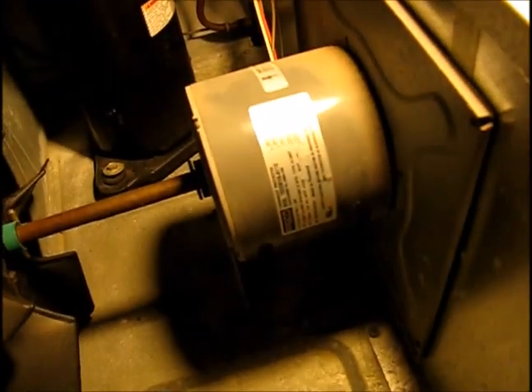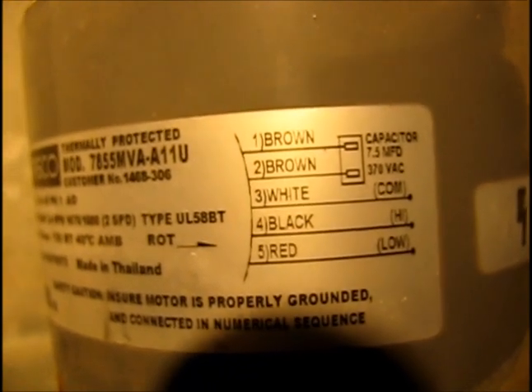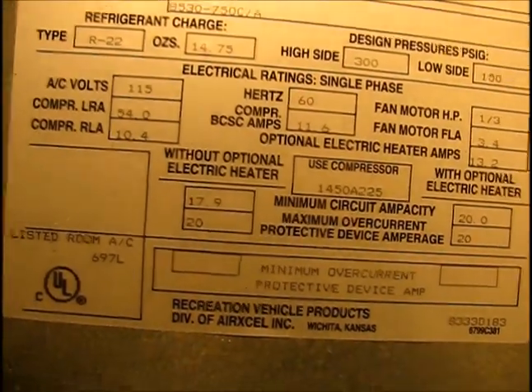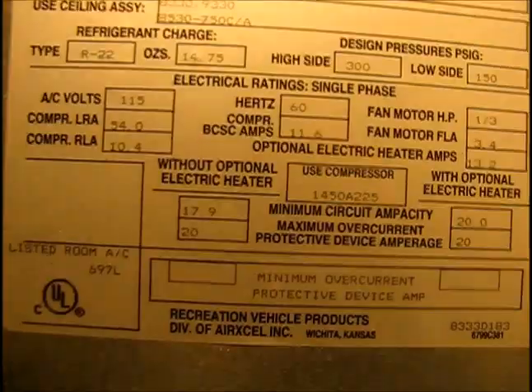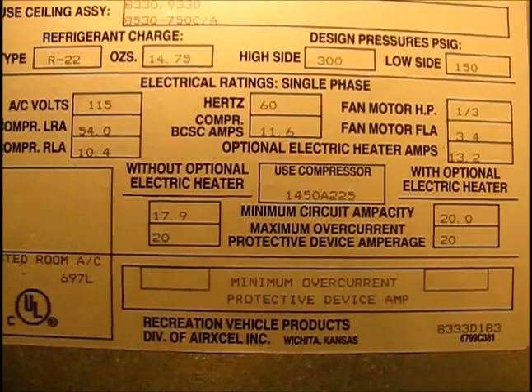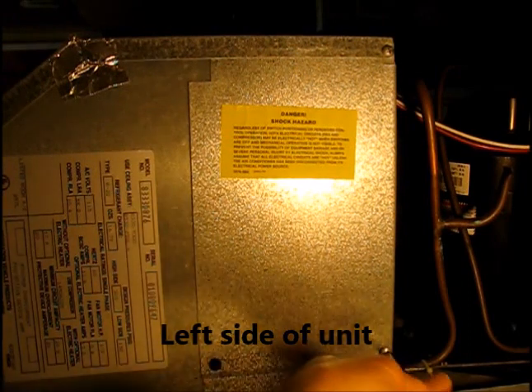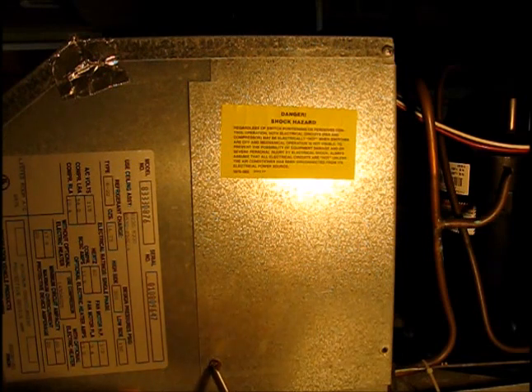Both sides off — now we can lift it up and off. Here's our fan motor that's failing to start up, and here's a look at our nameplate and wiring diagram. You can see the capacitor, which is what we're going to go after — and its brown wires. This is an Airxcel unit, recreational vehicle products division of Airxcel Incorporated, Wichita, Kansas. This AC unit has an access panel on the left side with just two Phillips sheet metal screws on the bottom that need to come out.